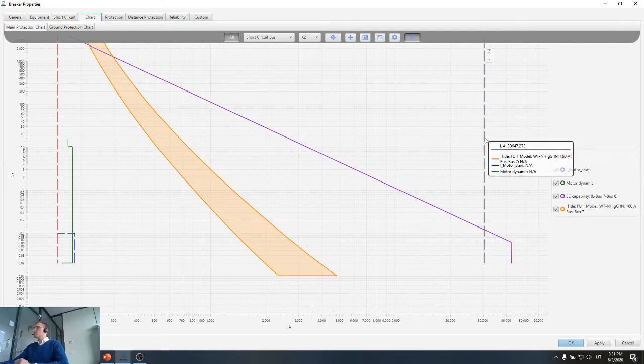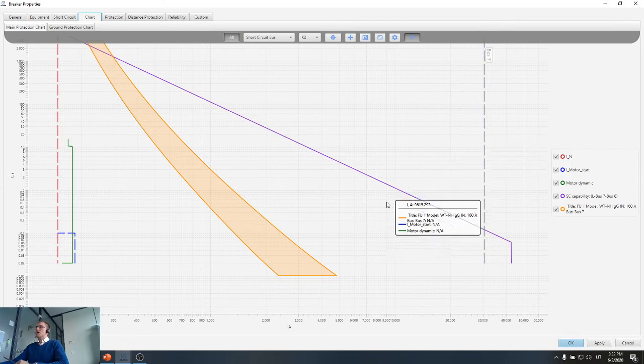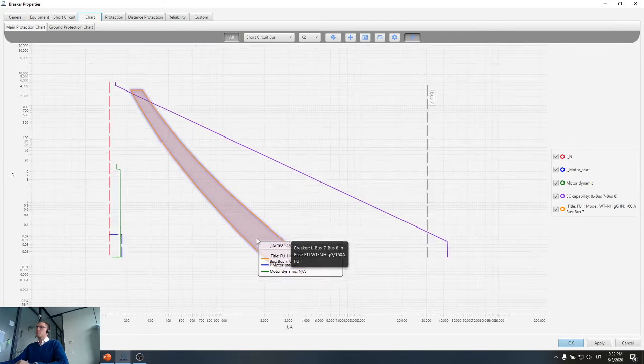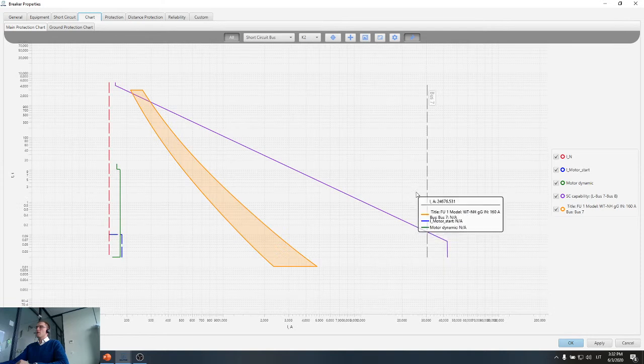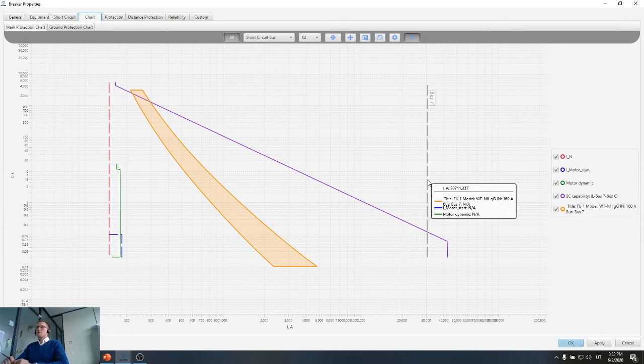So this current equals 30,000 amps. I can see this by moving my mouse cursor, and it provides the maximum possible short circuit current. Basically our protection device should be capable to protect equipment from this maximum short circuit current. How can we estimate if our protection devices are protecting the equipment?